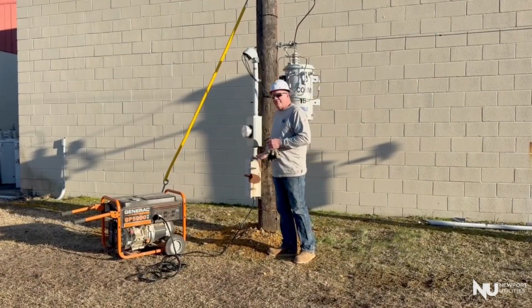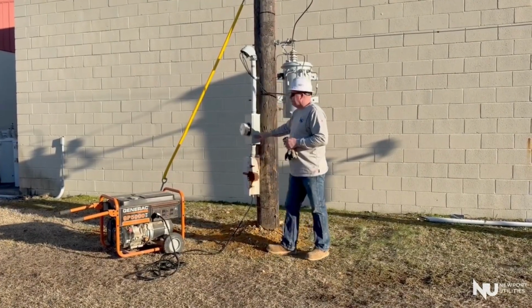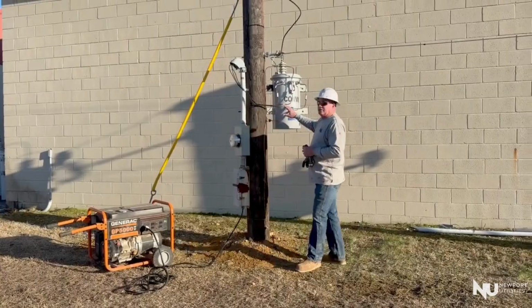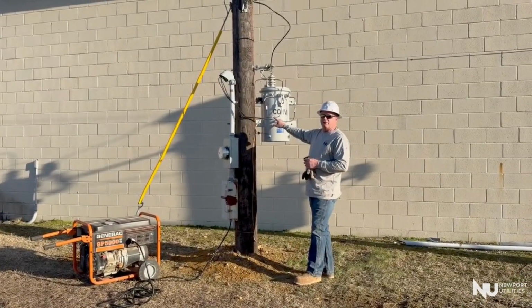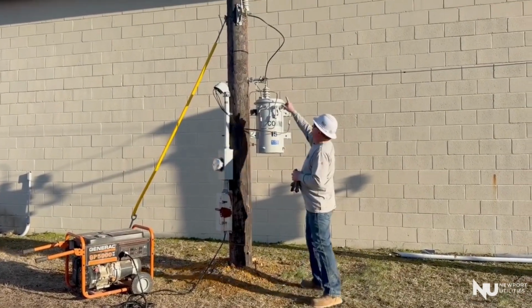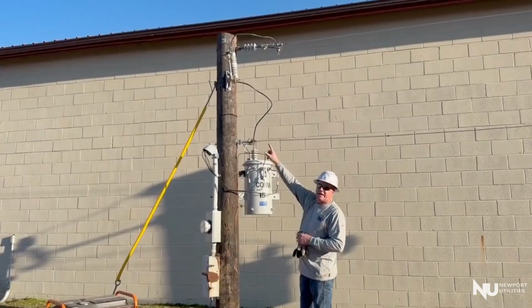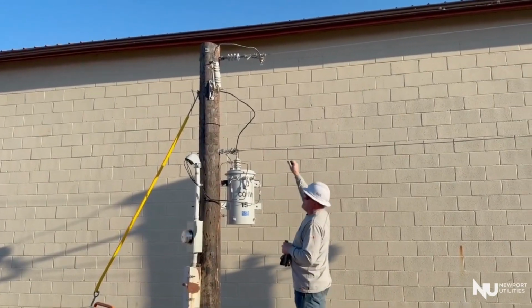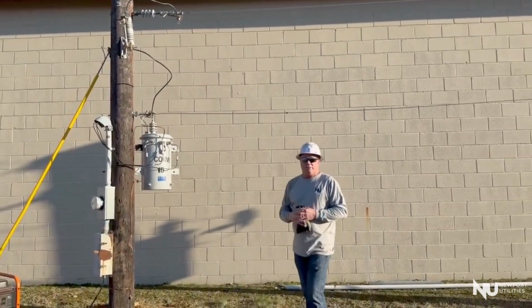It causes a backfeed through your panel, up through the meter, into the transformer at 120/240 coming backwards, causing a voltage of 7620 back out onto the line, and then into our work zone.